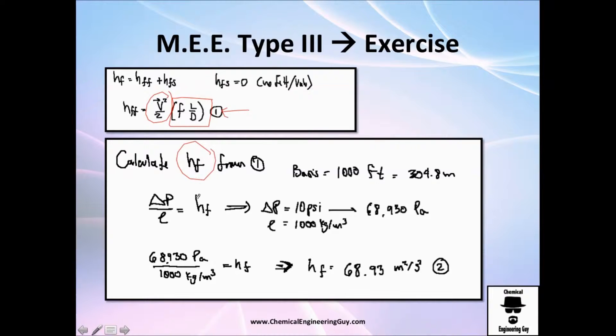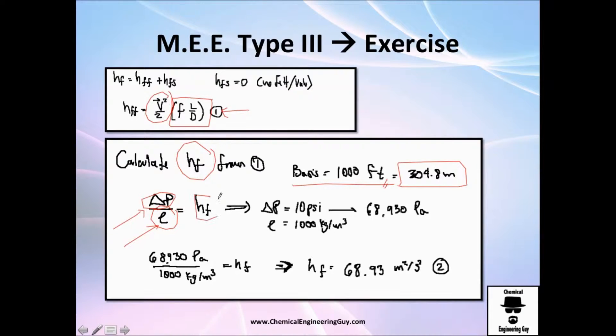Let's calculate the energy loss from equation 1. Using a basis of 1000 feet — converted to approximately 305 meters — and with the known water density, I calculate HF to be approximately 68.9 joules per kilogram. Keep this number in mind.